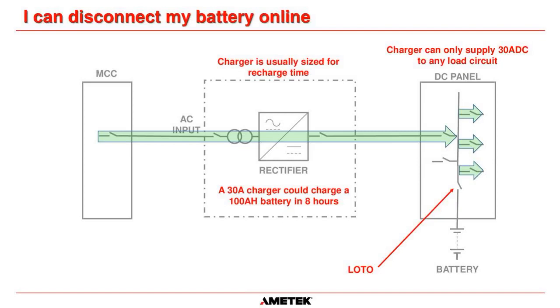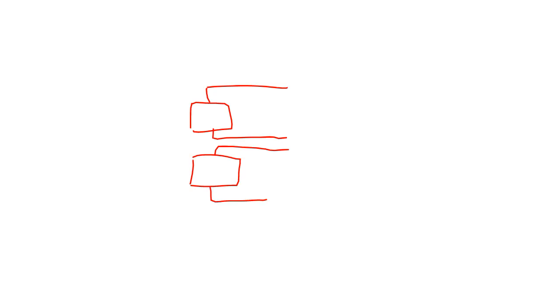If you have any two, let me see if I can do this. Go back to my whiteboard again. If you had this charger and this charger, okay, I'm going to probably draw it wrong. And let's say we connected these two chargers in parallel. So this is positive and it goes up to the positive on there. And then this is the negative and that goes down to the negative here. If this charger here, if its output was 50 volts and this charger here was 130 volts, if you look, they are now connected in parallel. So if you put your multimeter on this terminal here and this terminal here, which in truth is a parallel point between the two chargers, you're going to measure 130 volts.